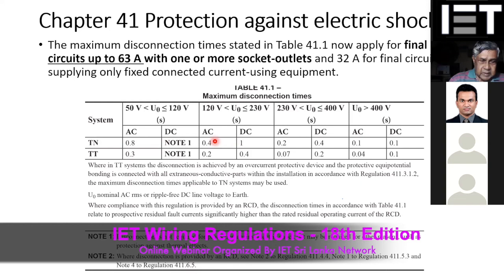After 32 ampere, you could go up to 1 second if it is a TT system, and up to 5 seconds for a TN system. But now this is extended up to 63 ampere. So you have to follow this maximum disconnection time for the earth faults.